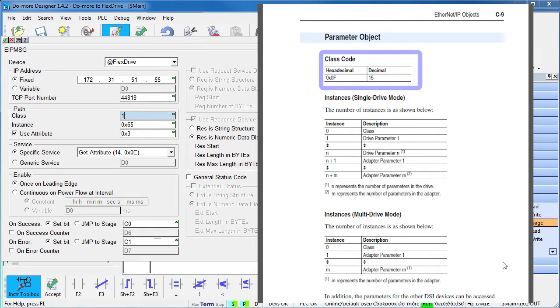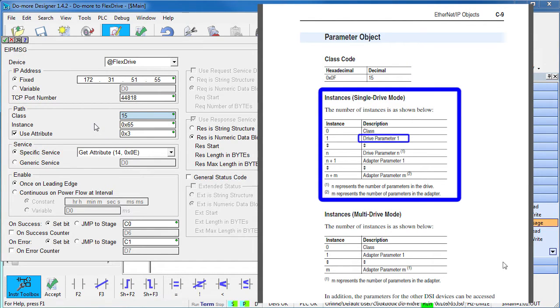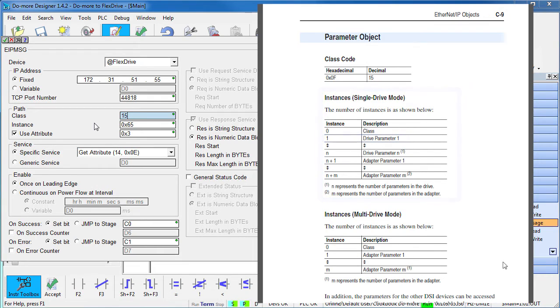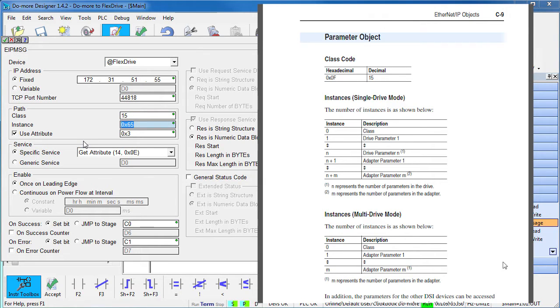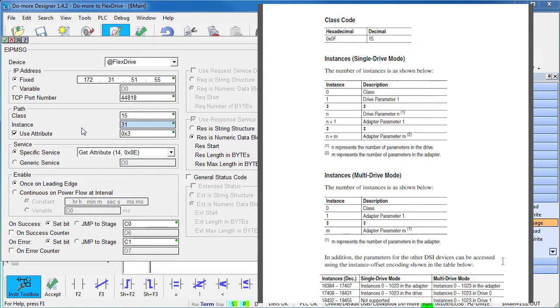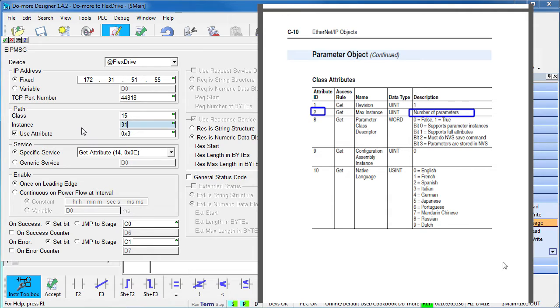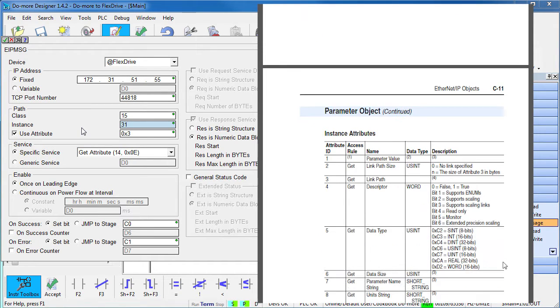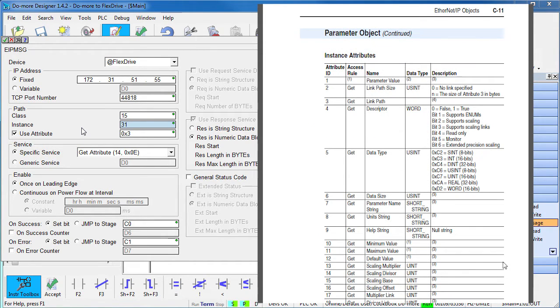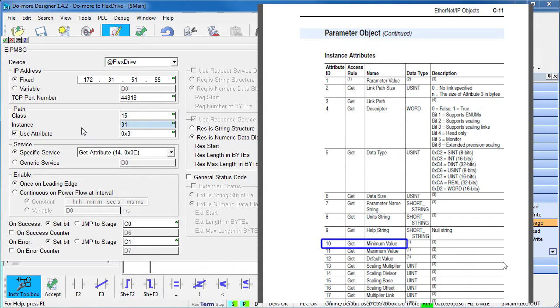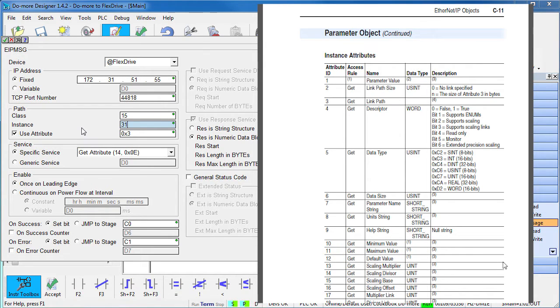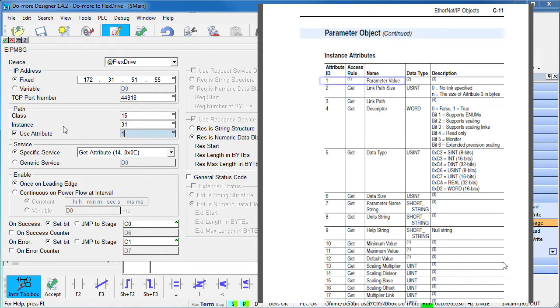This chart is telling me that the drive parameters are the instance numbers. That means these instance tables that we need have the same numbers as the drive's parameters. That's really convenient. In this example, we want the nameplate voltage, which is drive parameter 31, so that's also table or instance 31. It's also telling us that instance 0 is the class attribute table. And here is the format of that table. So if we wanted to know how many parameters are in this class, we would just specify instance 0 attribute 2. Here is the object template – the table format for these instances. The parameter value, the name, the units, the data type, the min value, the max value – everything we could want to know about each drive parameter. We want the value of the nameplate voltage for this first example – that's attribute number 1. So that number 1 goes here.